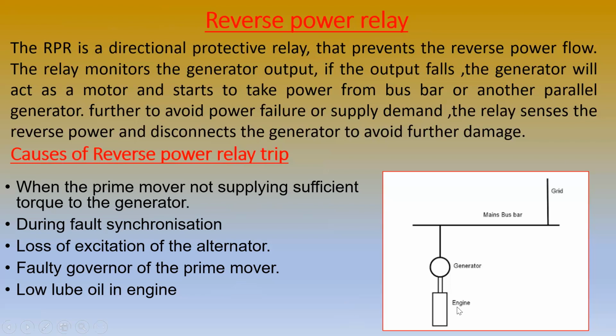As for the prime mover engine, maybe the engine is having low lube oil, maybe loss of excitation of the alternator, or a faulty condition of the governor of the prime mover. So this may be the reason why the engine cannot give sufficient mechanical torque to the generator. Maybe lube oil, fuel is very less, faulty governor, excitation loss. So this may be the reason why the engine cannot give the mechanical torque to the generator.